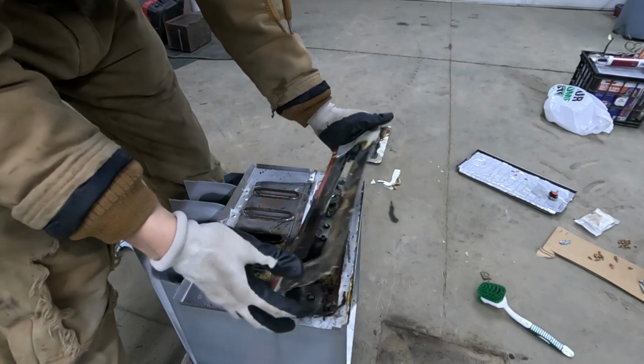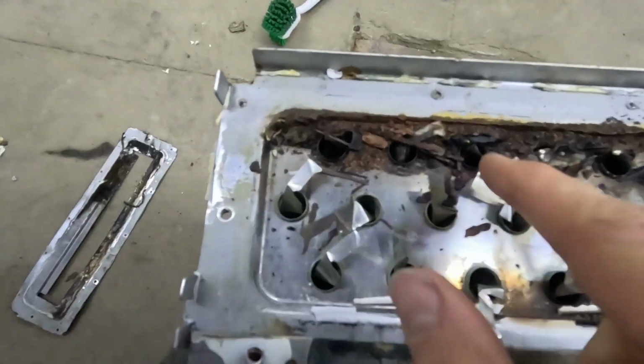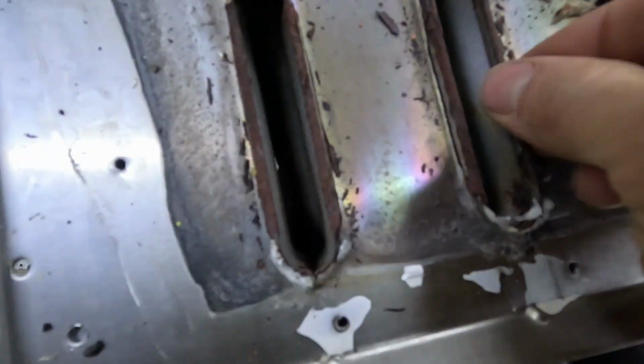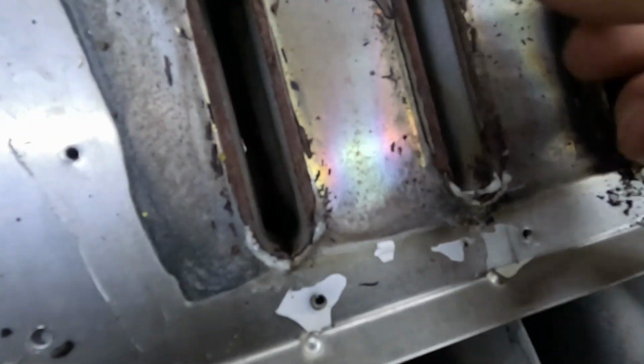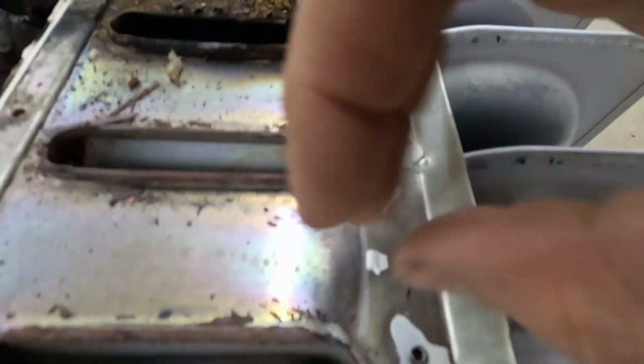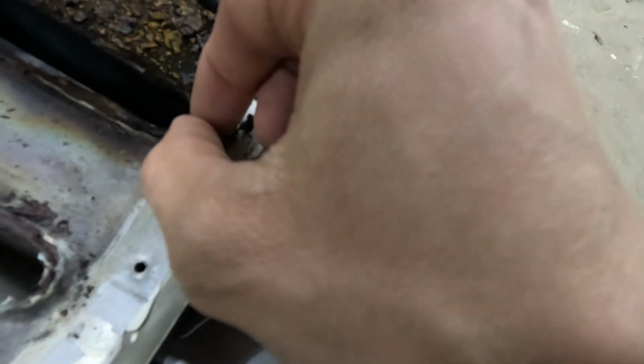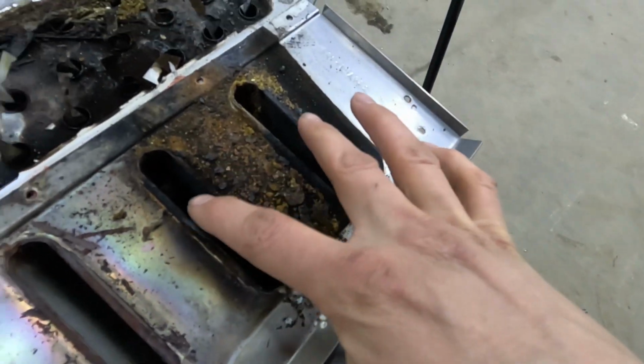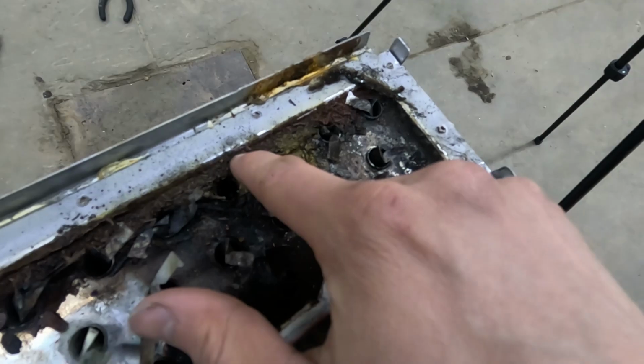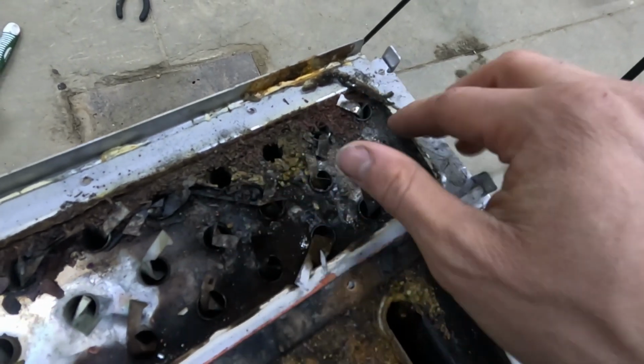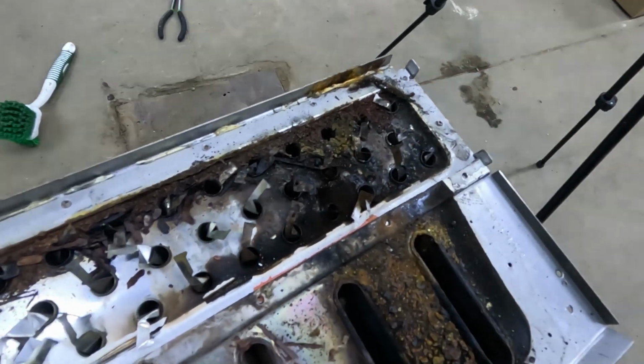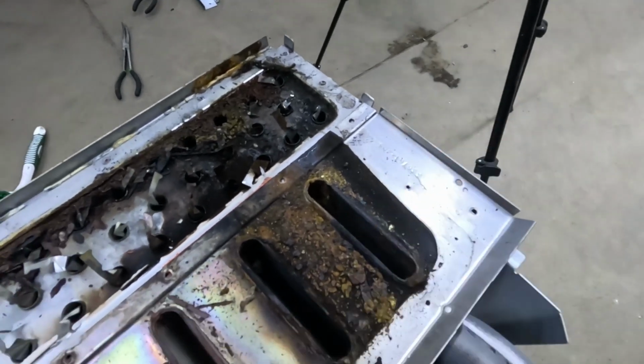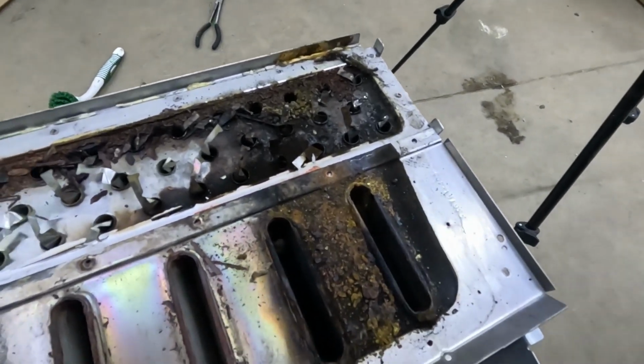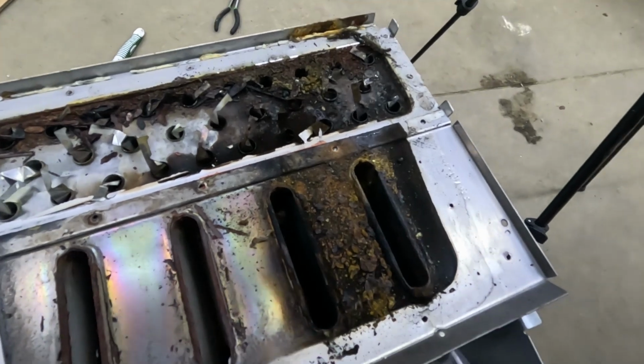what the heat exchanger looks like, so we can analyze their design and see if we like it. Oofda, there's that piece off. You can see they had some rust dropping off the primary heat exchanger right here where this edge is rolled over. There was some contamination like fiberglass, and it appears these ones got blocked up first. Once these blocked up, it just didn't have the right airflow through, and it began sooting, and then the whole thing sooted up.